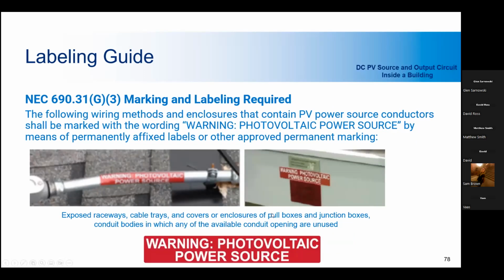I think I mentioned this earlier, but when you have DC wires running through conduit, you have to label it every 10 feet to make sure that whoever is working or whoever's in the vicinity knows that they're there. Many people will not like the look of this, so they run the conduit down through their attic where no one can see it, or they use microinverters so they don't have to see that, because the microinverters will convert the current to AC current right at the panel, and then you don't have the DC conductor labeling requirements.